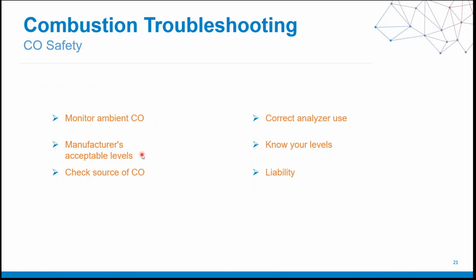Second one is the manufacturer's acceptable levels. In that manual snippet that I showed you in the beginning, it's very, very important to know and to understand what the acceptable levels are for carbon monoxide on the piece of equipment that you're working on. And you need to adjust the system accordingly so that you meet those specifications, because you don't want to put yourself at risk. You don't want to put the occupants at risk, and you don't want to have inefficiencies in the appliance.